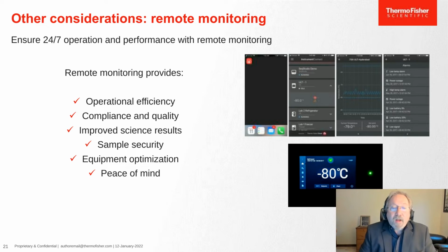When you have remote monitoring, it provides operational efficiency, compliance, and quality, answering all those questions. It gives improved science results, partly because if you're looking at your monitoring system, even before you get an alarm, if you see you want it a little tighter or it's not performing exactly right, you can put in a work order to have it looked at. Sample security is another benefit: remote monitoring tells you when the door was opened and how long it was opened. Equipment optimization shows indication that the freezer is running correctly, which gives you peace of mind that everything's fine. So in this case, we want remote monitoring.